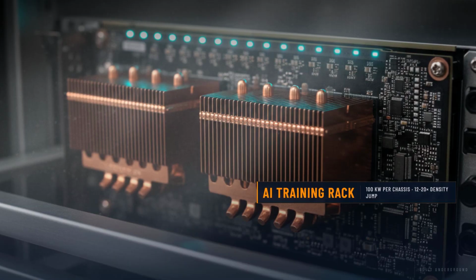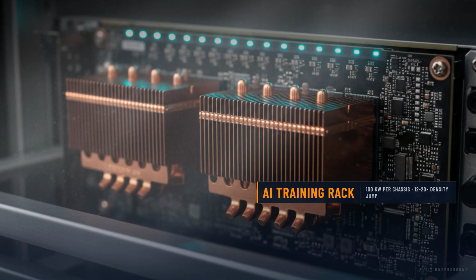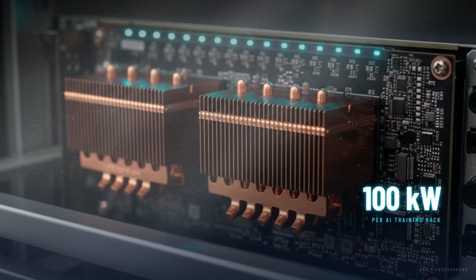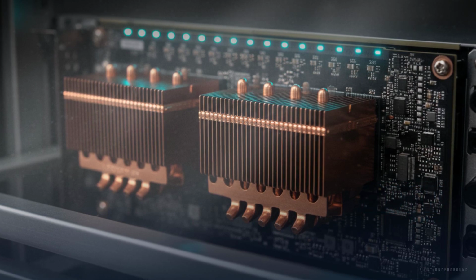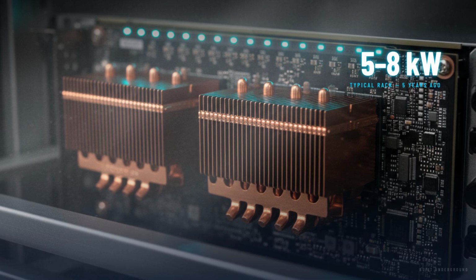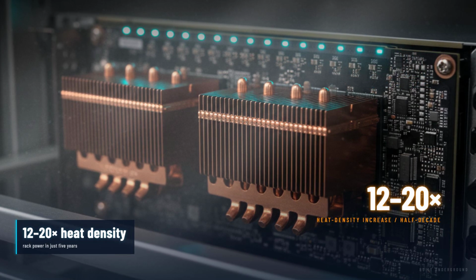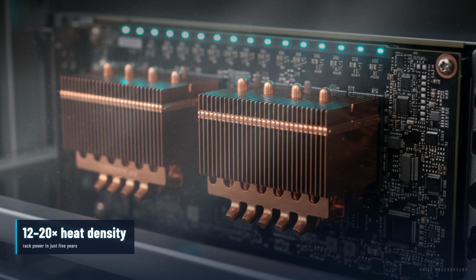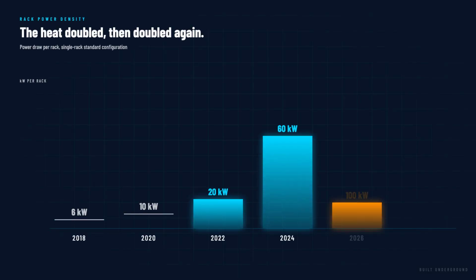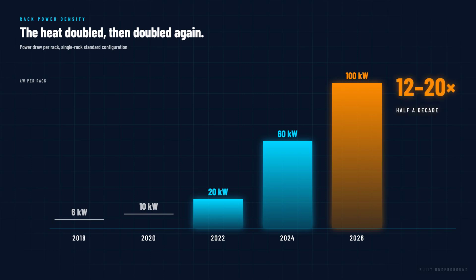A single AI training rack can now draw 100 kilowatts of power. 5 years ago, a typical server rack drew 5 to 8. That is a 12 to 20 times increase in heat density in half a decade. And here is the problem: the cooling systems that have kept data centers running for the last 30 years were never designed for this.